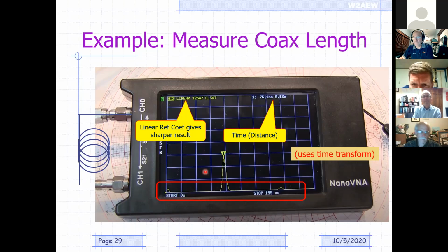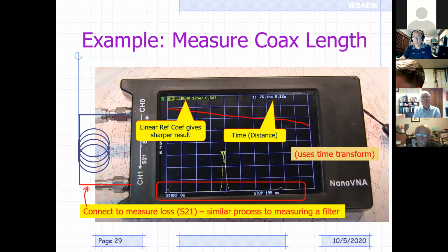So here we can see I put the marker on the peak and it's measuring the distance as 76 nanoseconds, or in this case just a little over 9 meters. It was a 21-foot coax cable that I hooked up to the end of this, and that's what it was measuring. Again, it uses a time domain transform, so the display here is actually in time, not in frequency. And of course, if you turn the transform off, you could connect up the coax to the other terminal and measure loss through the coax. You just don't do both of those at the same time. So measuring coax loss is a very similar process to measuring the low pass filter that I showed you earlier. Okay.